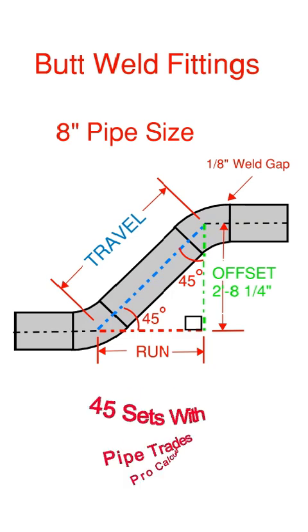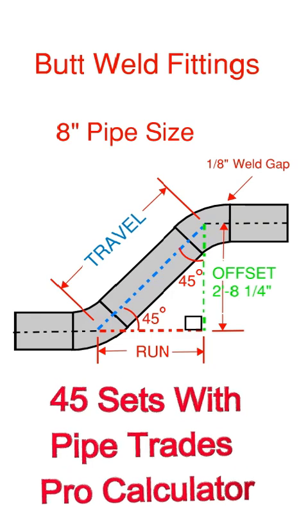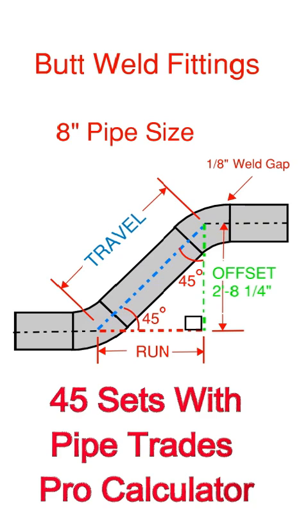We're dealing with 8 inch pipe size with the eighth inch weld gap. And we're going to be using the Pipe Trades Pro calculator to figure this 45 set. You can see the offset here is in green, and that's 2 foot 8 and a quarter. So I'm going to show you how to put this in the calculator.